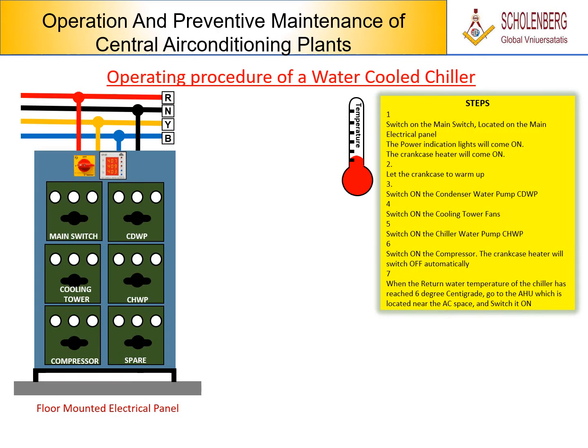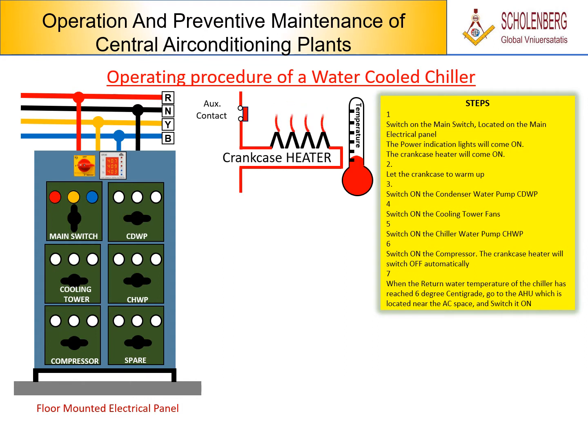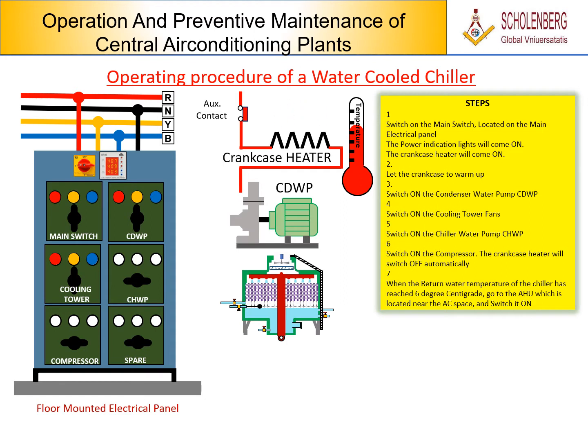Operating procedure of a water-cooled chiller. Steps. 1. Switch on the main switch, located on the main electrical panel. The power indication lights will come on. The crankcase heater will come on. 2. Let the crankcase warm up. 3. Switch on the condenser water pump, CDWP. 4. Switch on the cooling tower fans. 5. Switch on the chiller water pump, CHWP. 6. Switch on the compressor. The crankcase heater will switch off automatically.